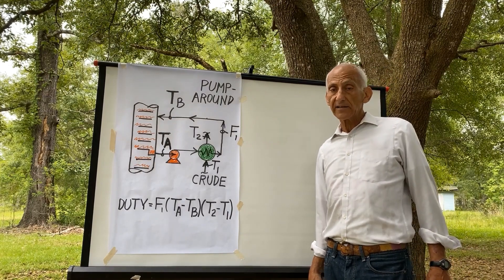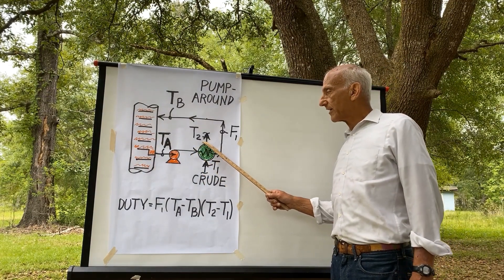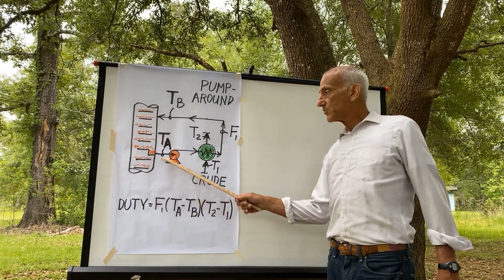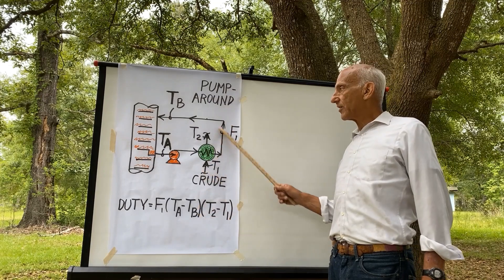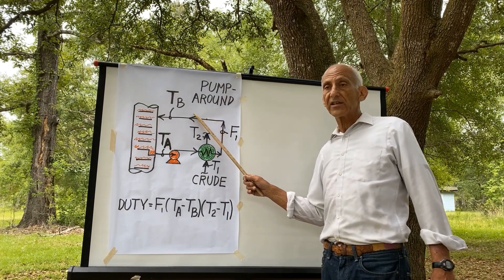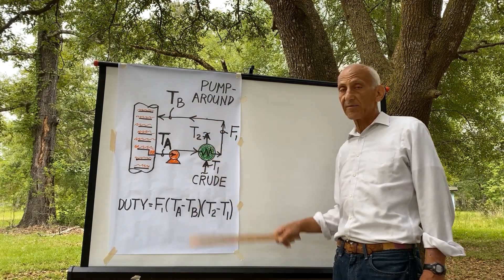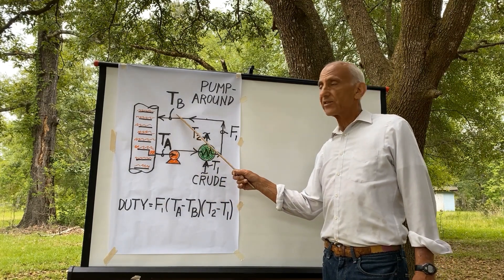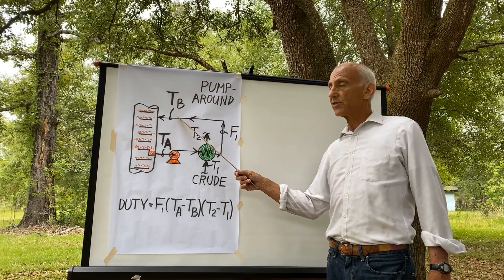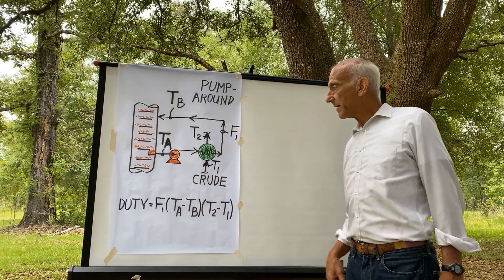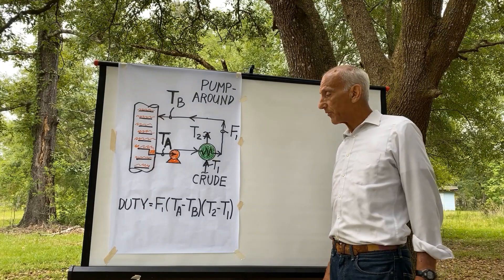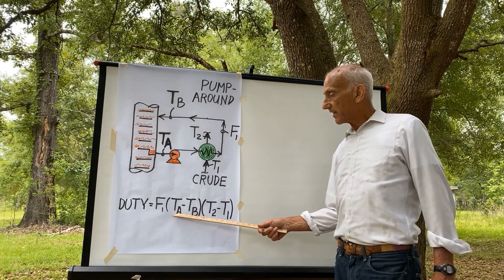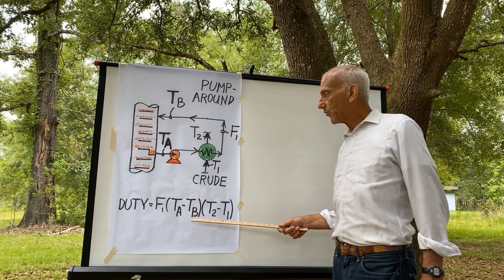Why? Because we are limited by the heat transfer capacity of this exchanger. As one increases the circulation rate, the heat transfer capacity of the exchanger remains the same because the surface area of the exchanger is constant. Then the pump around return temperature is going to go up. The amount of heat we remove for each barrel of pump around is proportional to the temperature difference between point A and point B.